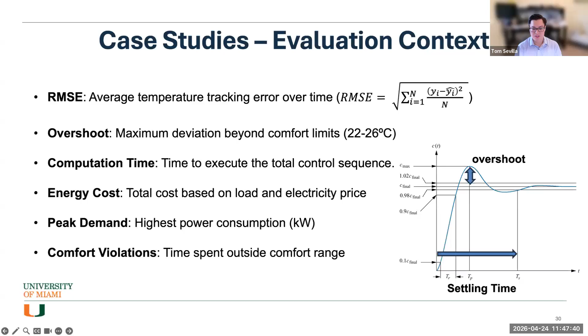So going into case one, we're looking at the fast transient disturbances. As you can see on the graph, we have a lot of steps, particularly for the people and lighting load, and these are occurring around every 30 minutes. From here, we can see that the PID cannot maintain the set point. It's fluctuating all the time. You have an RMSE around 1 degree C, and its overshoot is almost 3 degrees C. Now, if you look at the ideal MPC, the overshoot's much better. You have much more improved tracking. However, your compute time went from 0.002 seconds to around 34 seconds. So it's a much more expensive type of control.